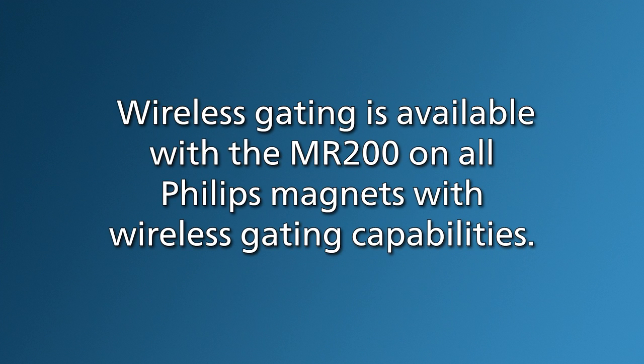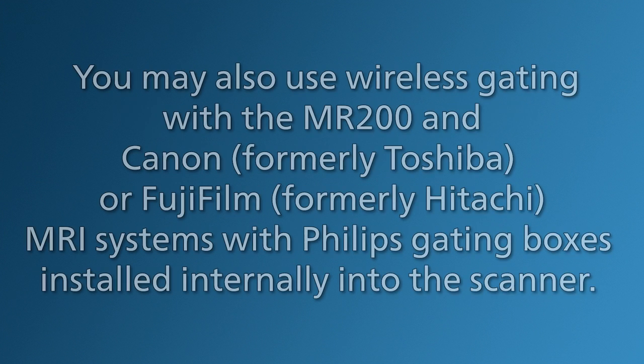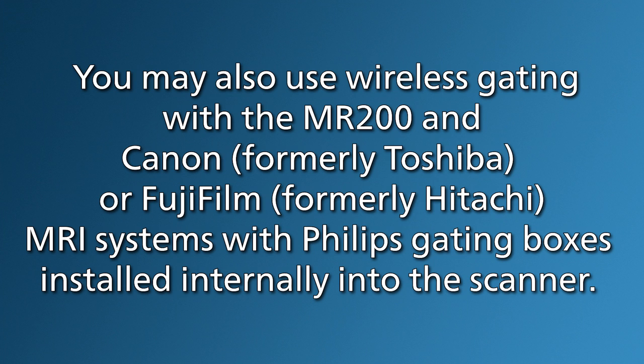Wireless gating is available with the MR200 on all Philips magnets with wireless gating capabilities. You may also use wireless gating with the MR200 and Canon, formerly Toshiba, or Fujifilm, formerly Hitachi, MRI systems with Philips gating boxes installed internally into the scanner.